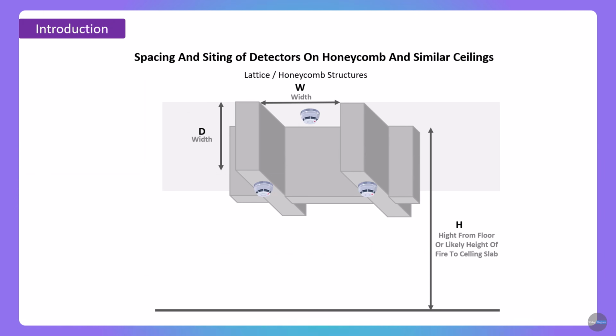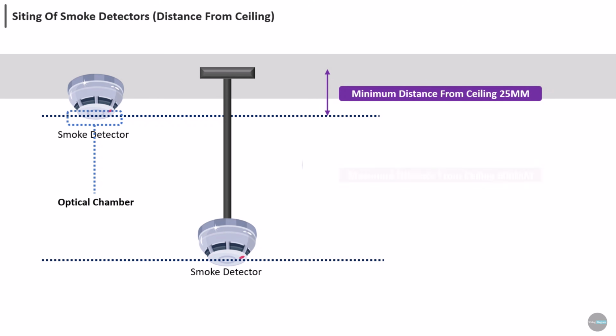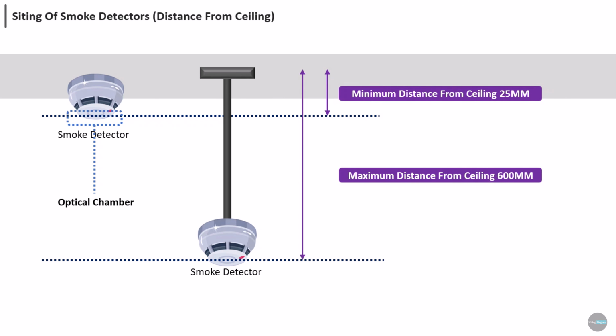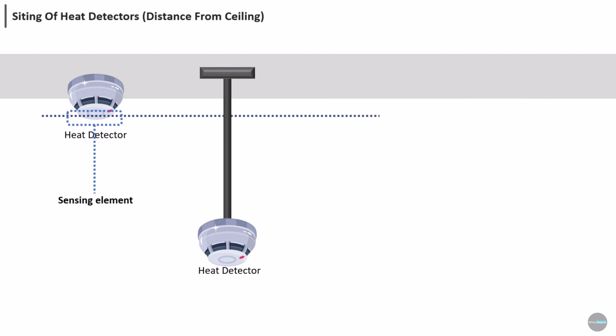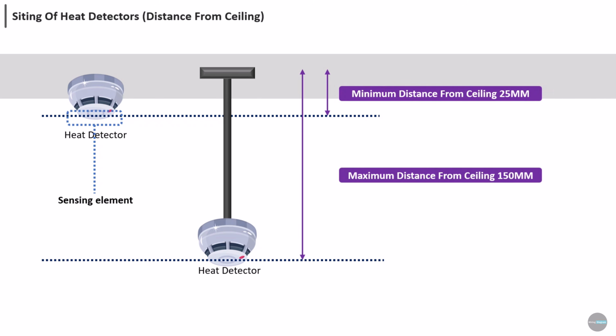So let's get started. Siting of smoke and heat detectors. Smoke and heat detectors are always mounted on the ceiling. For smoke detectors, the sensing chamber must be at least 25 mm from the ceiling and no more than 600 mm. When using a junction box or mounting plate, the distance between the detector and ceiling should not exceed 600 mm. For heat detectors, the sensing chamber must be at least 25 mm from the ceiling and no more than 150 mm.